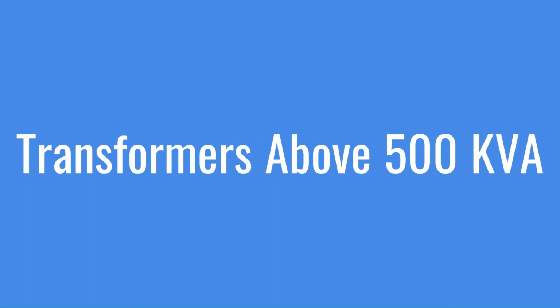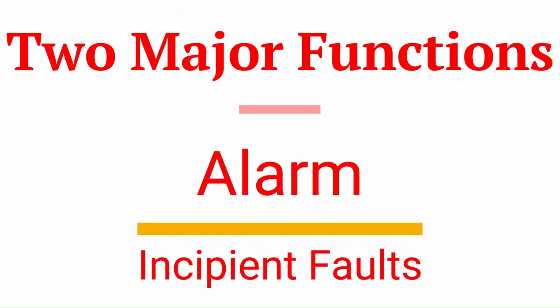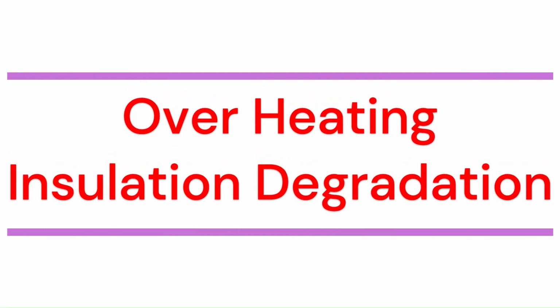Buchholz relay is generally used for oil-filled transformers whose rating is above 500 kVA. This relay performs two major functions. First, it is used to give an alarm in case of incipient faults. We can say that it gives an alarm when there is a less severe condition. Incipient faults are minor faults that occur in a transformer and may gradually develop into more serious issues if not addressed promptly. For example, minor overheating or insulation degradation.